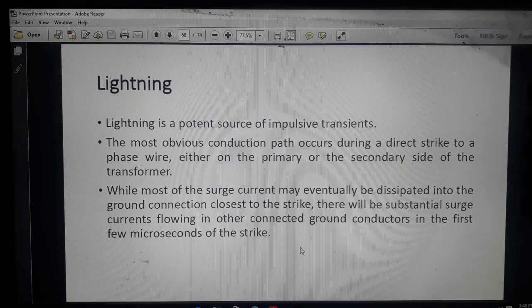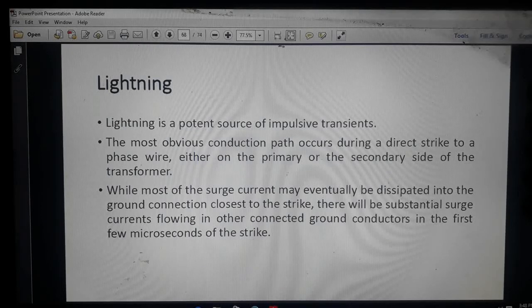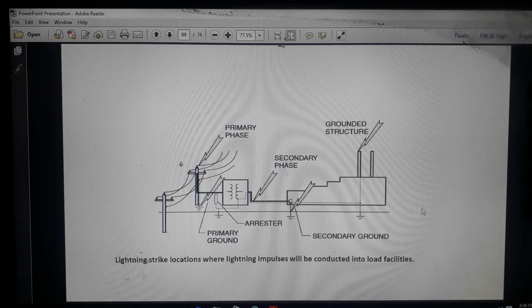If we are talking about our transformer or transmission system, there is grounding. If lightning strikes any phase conductor, then it is grounded through the neutral. And sometimes we use a lightning arrestor. An arrestor provides high resistance at power frequency and low resistance at high frequency. If lightning happens near, the arrestor absorbs that lightning and grounds it, which protects our transmission system, generating system, whatever we have.